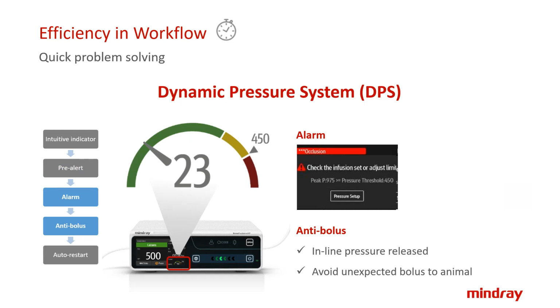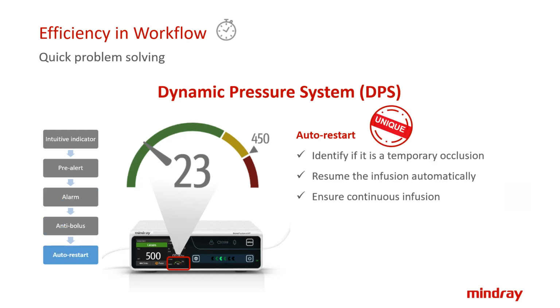And if the pressure is over the limit and falls within the red area, an alarm is triggered on the screen, asking the veterinarian to check the infusion set or adjust the limit. At the same time, the system does the anti-bolus, releasing the pressure inside the tube to avoid an unexpected bolus to the animals and make sure of their safety. After the occlusion is eliminated, the system performs an auto restart. It will identify if this is a temporary occlusion, and then resume the infusion automatically, which makes sure of continuous infusion.